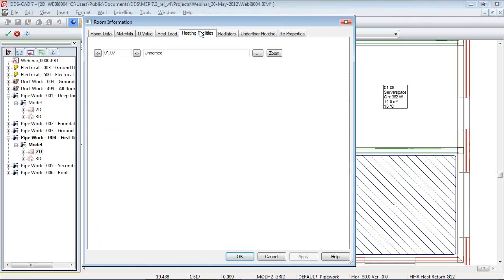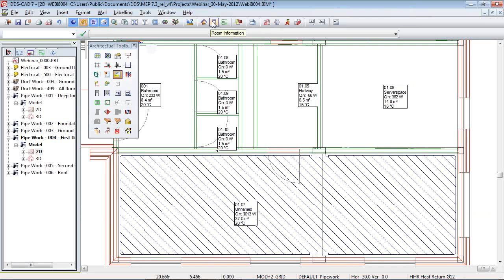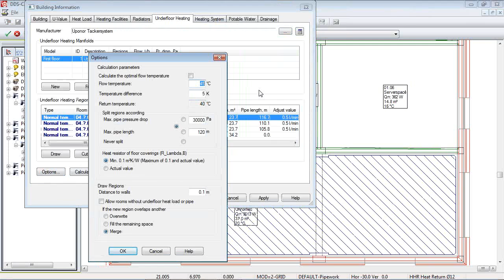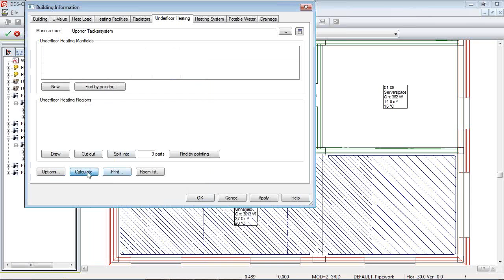Right. For the options on the calculation, we can start with the optimum temperature, like 45, for underfloor heating. When pressing calculate, for each room in which underfloor heating is detected, we get a notification that the outcome of the heat flow is not sufficient. So in the room we need 3 kilowatts, and the underfloor heating is only providing 2.2 kilowatts. So the underfloor heating is automatically divided into systems. So we have 1, 2, 3 systems in here, and when we put in the part text and ask for information on the system, we can see that we have 250 as the pipe distance, and the total length is 105 meters, and this is set as normal temperature.